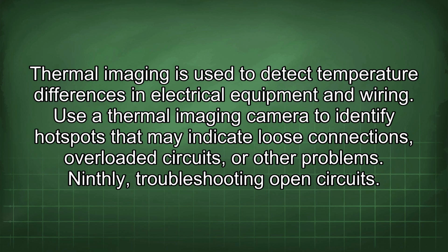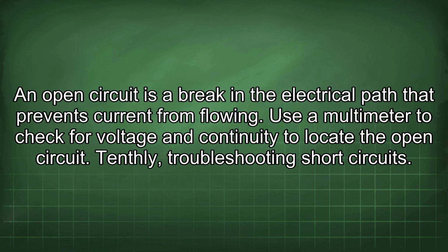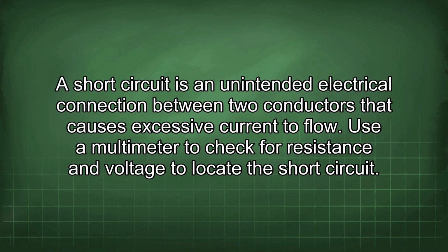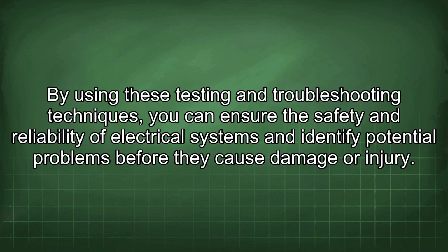Ninthly, troubleshooting open circuits. An open circuit is a break in the electrical path that prevents current from flowing. Use a multimeter to check for voltage and continuity to locate the open circuit. Tenthly, troubleshooting short circuits. A short circuit is an unintended electrical connection between two conductors that causes excessive current to flow. Use a multimeter to check for resistance and voltage to locate the short circuit. By using these testing and troubleshooting techniques, you can ensure the safety and reliability of electrical systems and identify potential problems before they cause damage or injury.